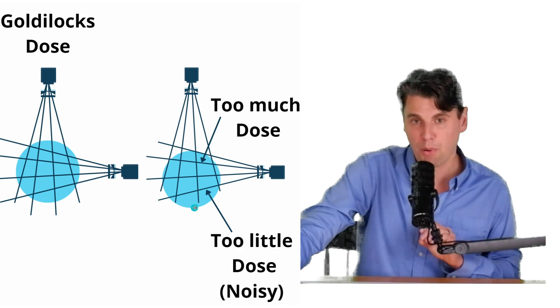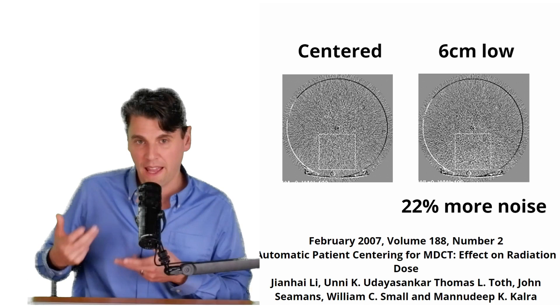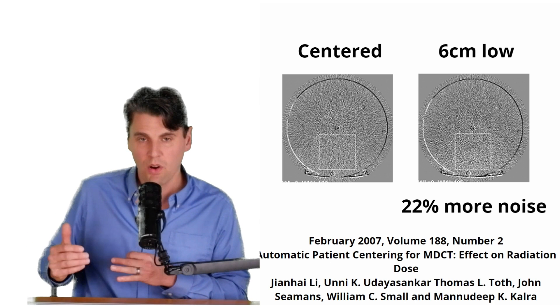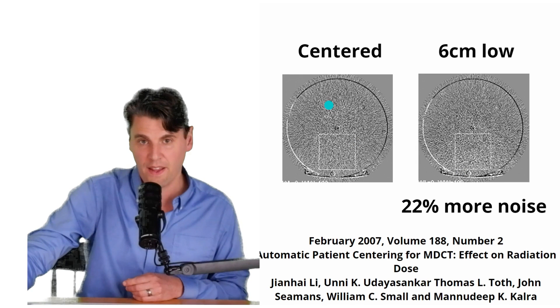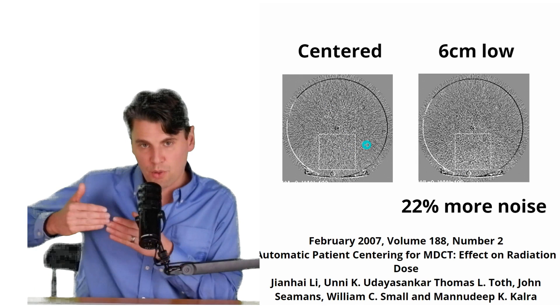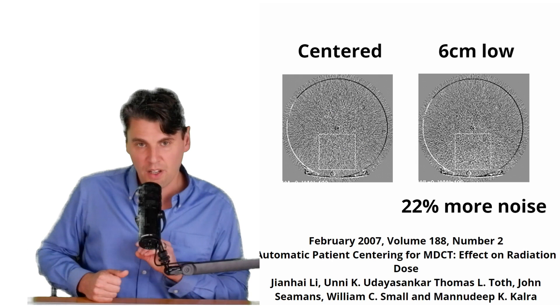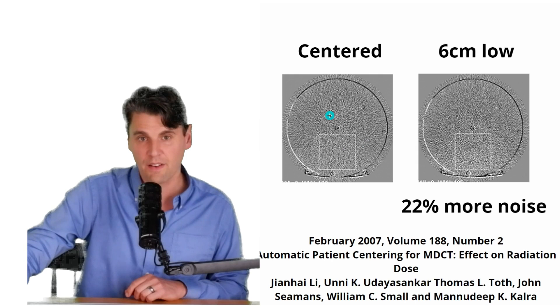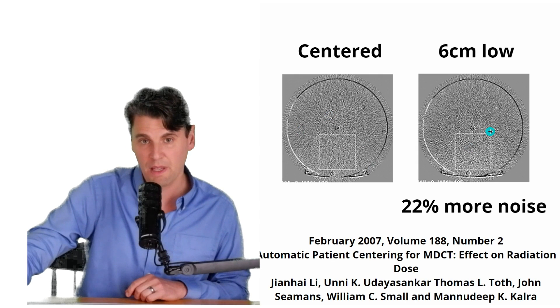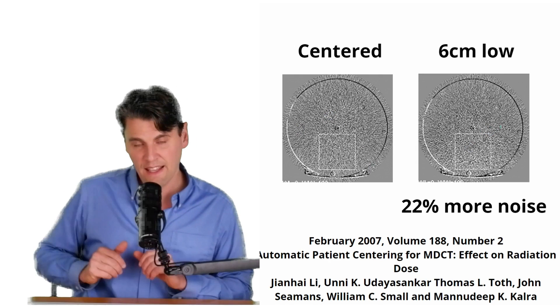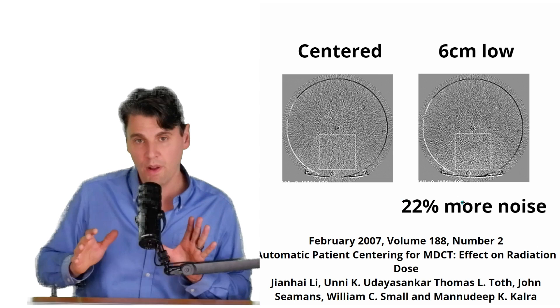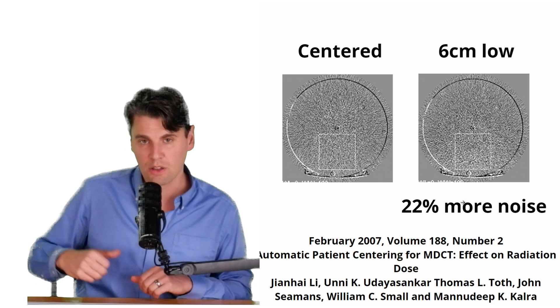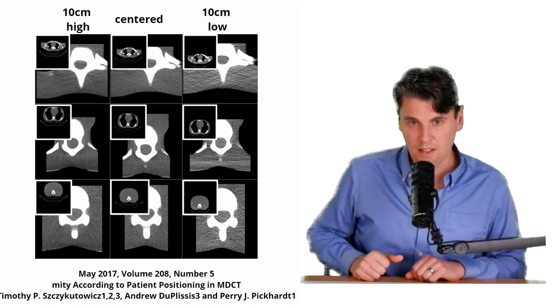This is joint work by NGH and GE a number of years ago, looking at that effect on the centering. And in this case, it's a centered phantom, and you're looking at subtraction between adjacent images to look at the noise map. So in the case of the centered phantom versus in the case that you're 6 centimeters too low, it was measured to be 22% more noisy in those lower parts of the image.